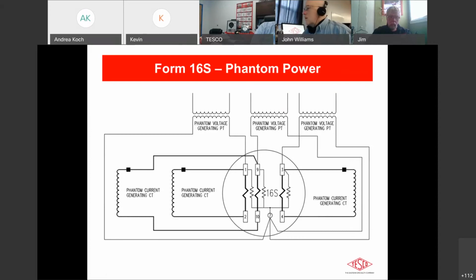I did realize one thing that I forgot to mention earlier. One of the things with regard to phantom loading and test boards is the residential applications with service disconnects built into the meters, right? So your 1S, your 2S, and your 12S meters. A lot of the meter manufacturers put high-powered relays in there to do the disconnect switching, which require a lot of current, a lot of VA to open those disconnects and close them.